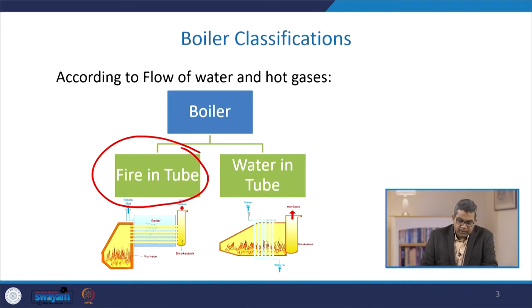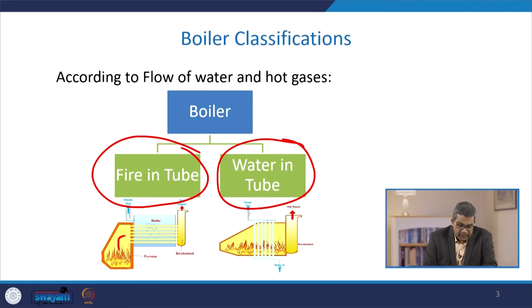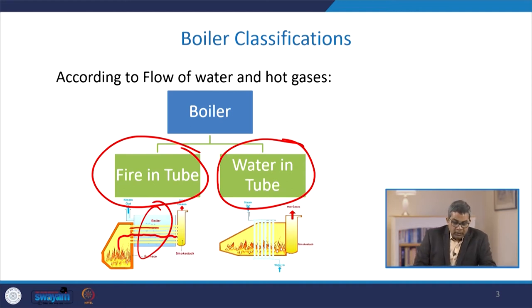Various boiler classifications have been suggested by various workers. One classification is based on the flow of water and hot gas — this may be fire-in-tube or water-in-tube, because basically the boiler is an assembly of tubes and shell. In fire-in-tube, the flue gases are within the tube system and the bundle of tubes is submerged in water. Upon heating, you can produce steam, so fire is on the tube side.